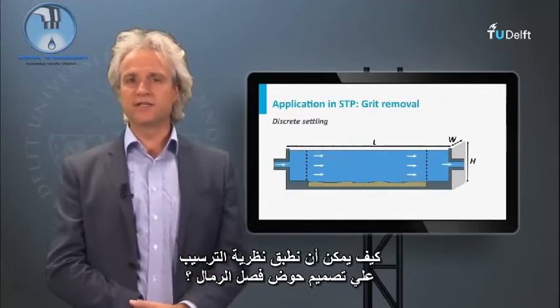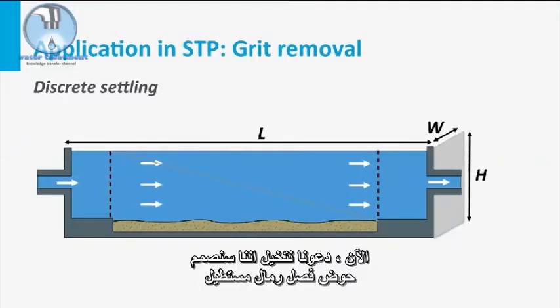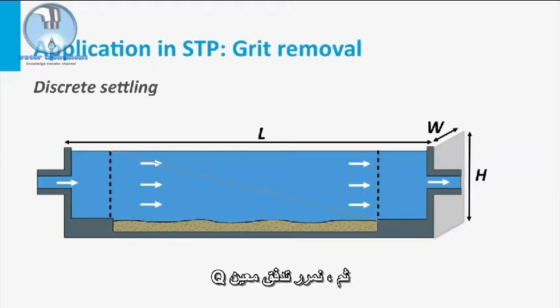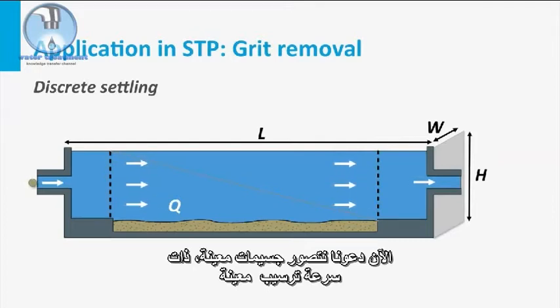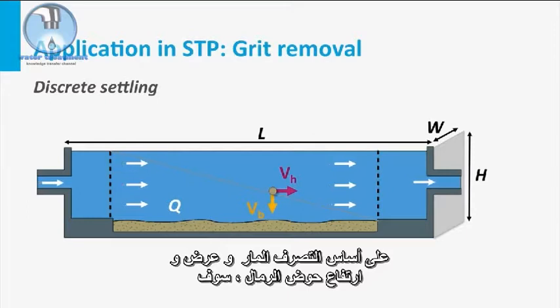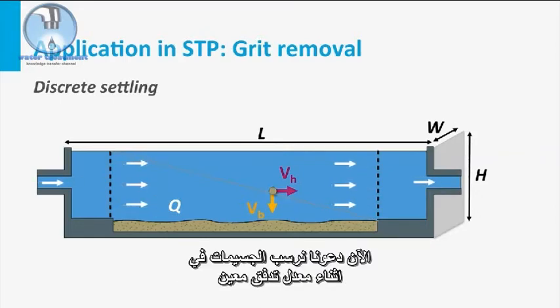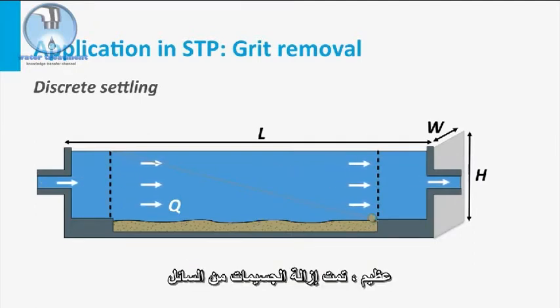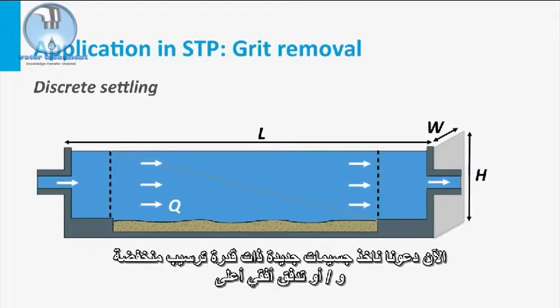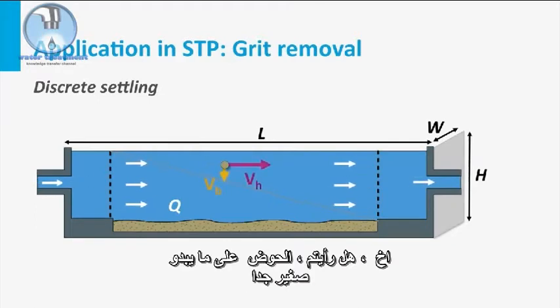How can we apply the settling theory to the design of our grit chamber? Let's imagine we are going to design a rectangular grit chamber with a certain length, height and width, and apply a certain flow rate q. A certain particle with a given settling velocity will flow with a certain horizontal velocity based on q and the chamber dimensions. If the particle is sedimented at the given flow rate, it is removed from the liquid. However, with a lower settlability or a higher horizontal flow, the tank is apparently too small.